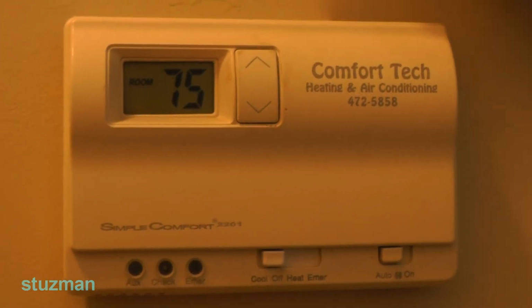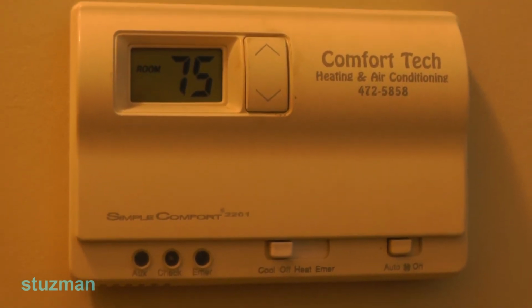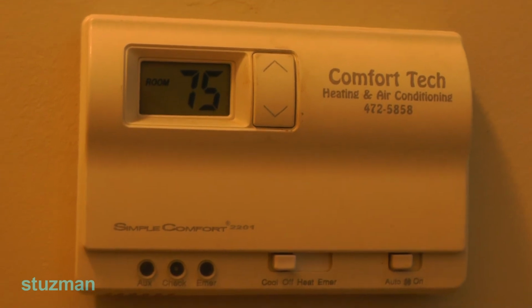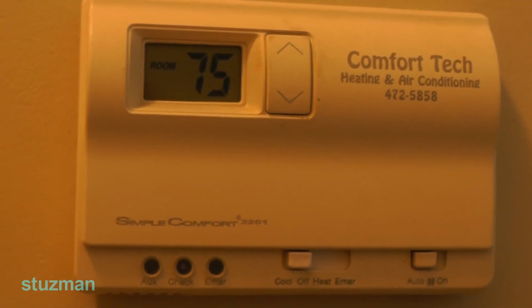All right guys, you can see that we started at 78, we're down now to 75 and it's still coming down. It's probably been running about an hour and a half, and it's a lot of space in here to bring the temp down. Let's go ahead and wrap up this video. So you see if you do have a problem like that with your evap fan motor, hopefully you got the steps now to troubleshoot it. Also, if your motor does run backwards, you now know you can reverse any two of those wires going down to the stator windings, and that will make the motor run in the reverse direction. Hopefully you find the video helpful. I appreciate you guys watching, because this is a long one, but I wanted to leave all the steps in there so you can see exactly what happened here. Hopefully it helps you guys out if you want to tackle this job yourself, and in the process save yourself some money.